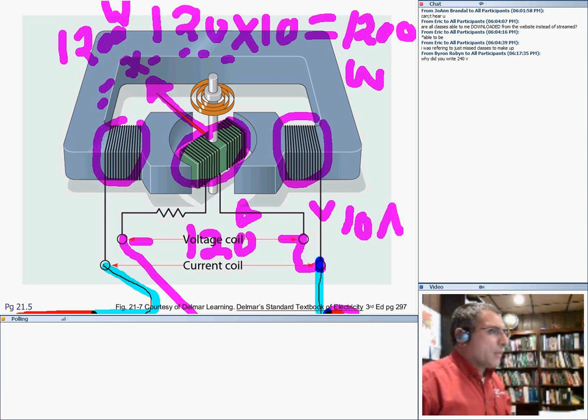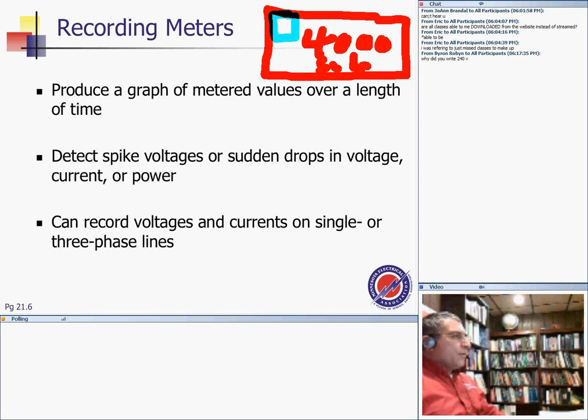So moving from these into more sophisticated equipment, we have a 4000 amp switch here. A lot of customers want to know a lot of stuff about their switchgear. If you have a 4000 amp switchgear, you have a digital multi-function meter that you put right here in the switchgear. It gives you a graph of metered value over a length of time, detects spikes in the voltage, sudden drops in the voltage, the current, the power, and records the voltage and the current.